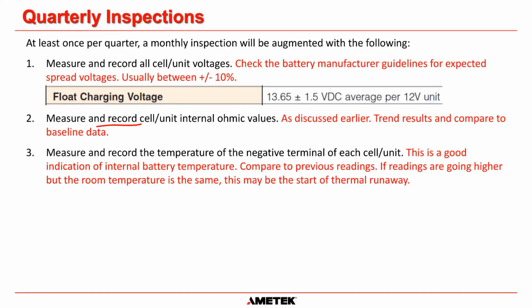You also have to measure and record cell unit internal ohmic values, and then trend those results and compare them to the baseline data, as we mentioned before. There's no point in just taking those values and not doing anything with them. You have to trend them against previous results. And then measure and record the temperature of the negative terminal of each cell or jar. That is a good indication of the internal battery temperature, and then you have to compare that to previous readings.